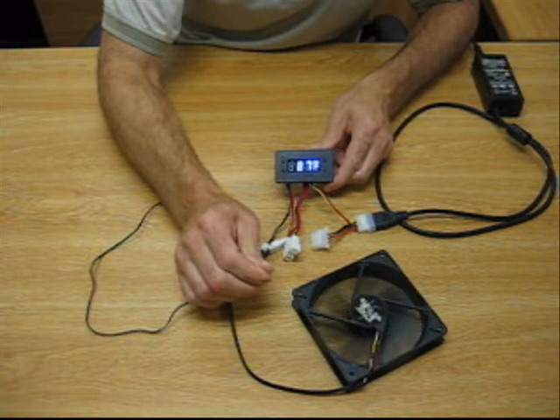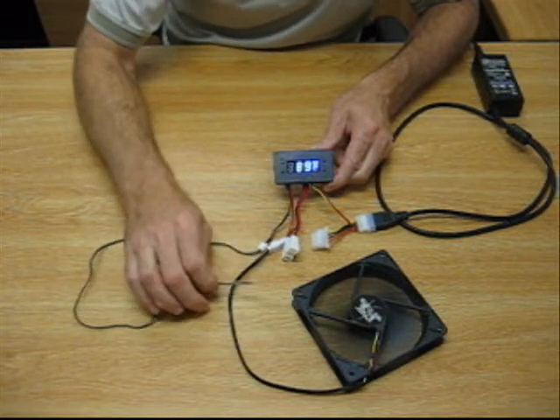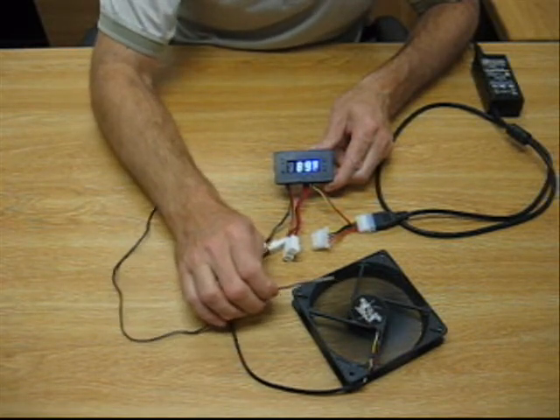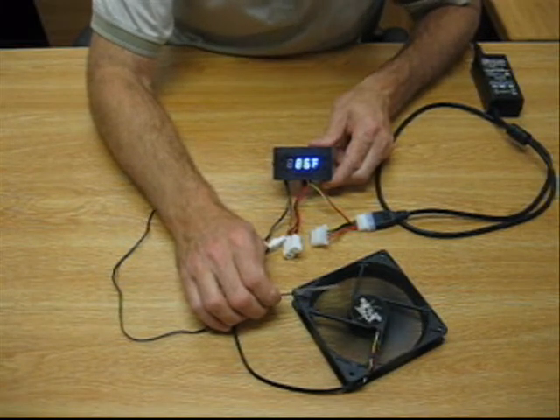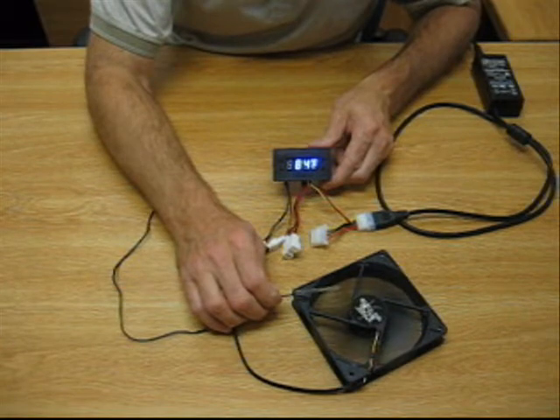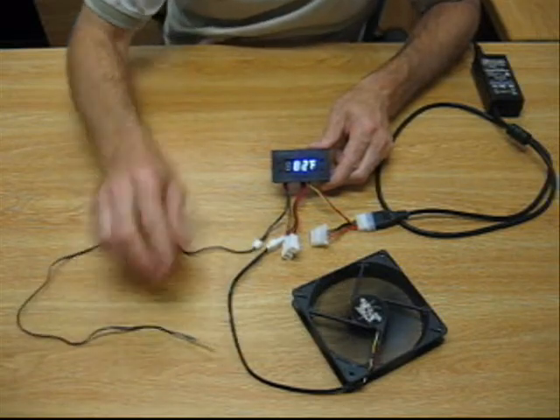Let's heat up the probe. Get it to our start temperature of 87 — fans go on. As it cools down, when it gets down to our desired stop at 83, the devices will go off. There you go.